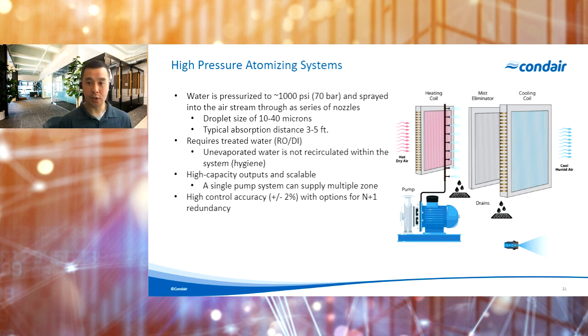Now, the efficiency will also depend on the entering air conditions, so the temperature and the relative humidity, the air velocity, as well as that available absorption distance. So with higher velocities or even shorter absorption distances, that contact time is going to be shorter. So we would typically expect a lower evaporation efficiency in those types of conditions. For both systems, evaporative media and high pressure atomizing systems, we do generally try and design around a 400 to 500 feet per minute air velocity or duct velocity.